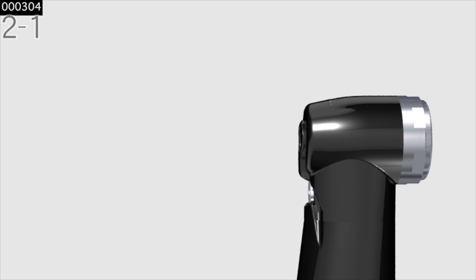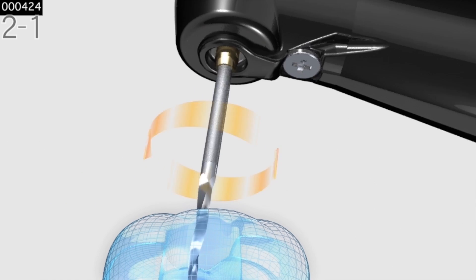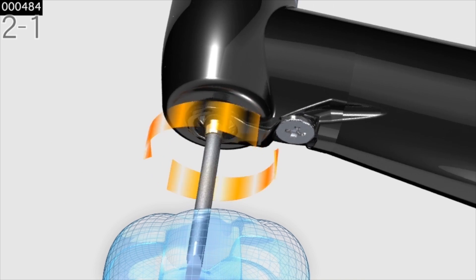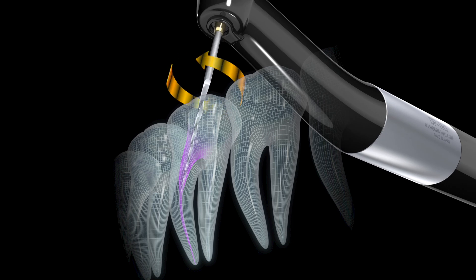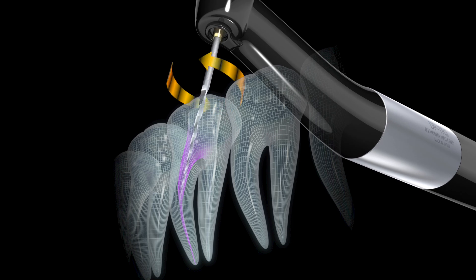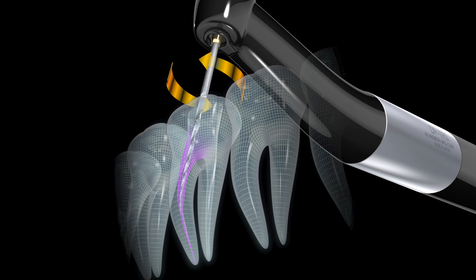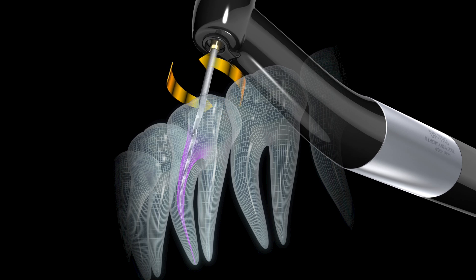The way OTR works is that you enter a torque limit value into the handpiece and then operate the file in a normal rotary motion. As soon as the motor senses that the file has reached the programmed torque limit during engagement, the file will automatically disengage 90 degrees in a counterclockwise direction, and then after disengaging, it immediately spins back into clockwise rotary motion — unless the same torque limit is reached once again, in which case it will go back again 90 degrees to disengage, followed by continuous rotation.